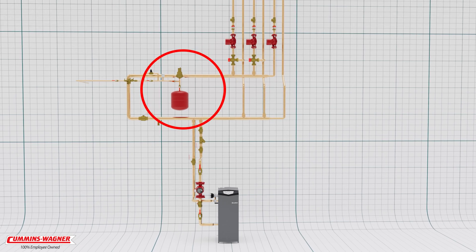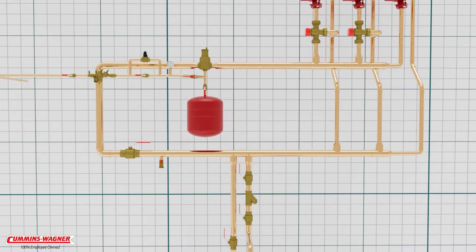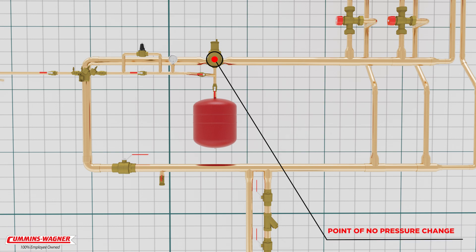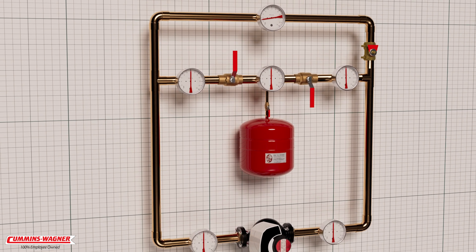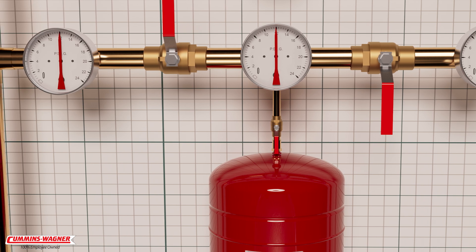The point where the expansion tank is connected to the system is known as the point of no pressure change. We've been taught for many years to pump away from this point, but why? With this model we can explore that question and hope to provide you with a better understanding of the point of no pressure change and why we always pump away from it. We start with the expansion tank isolated from the system with ball valves.